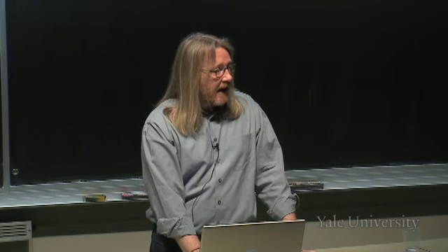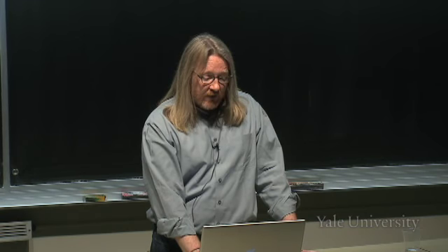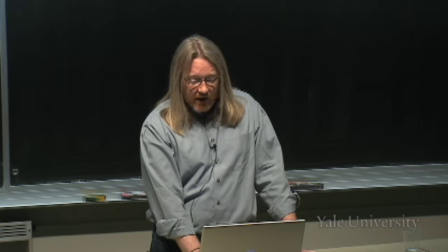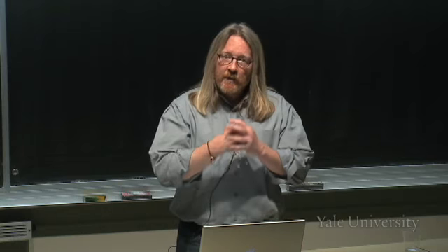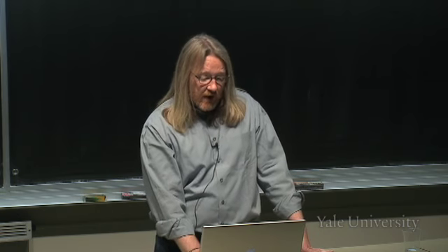Another difference in this design is instead of having a metal head which moves against a metal ball which moves against the polymer socket, this one has a ceramic head. And the friction between ceramic and a polymer is even less than the friction between a metal and a polymer. These are also much lighter. Ceramics are lighter. They're very strong, and you can create a joint that lasts even longer with materials like this.